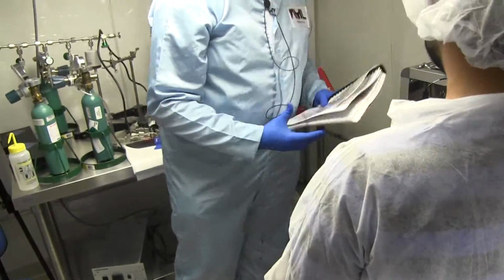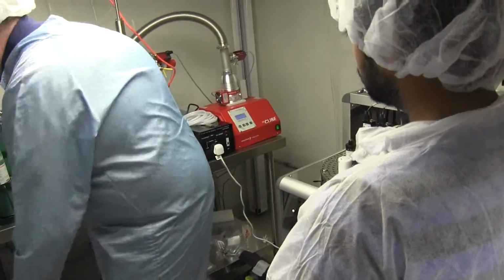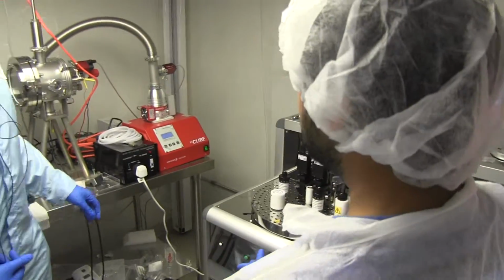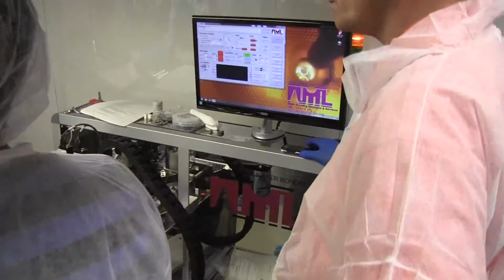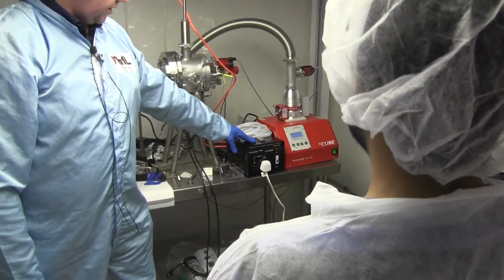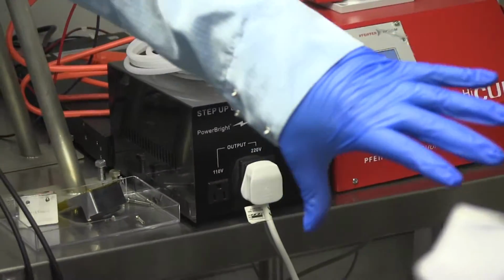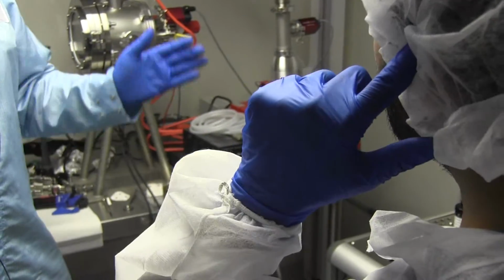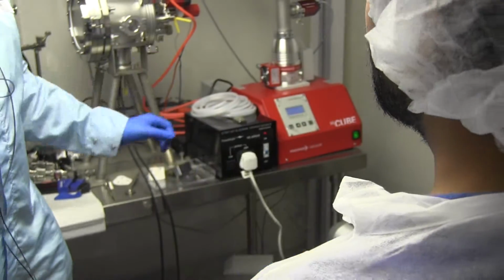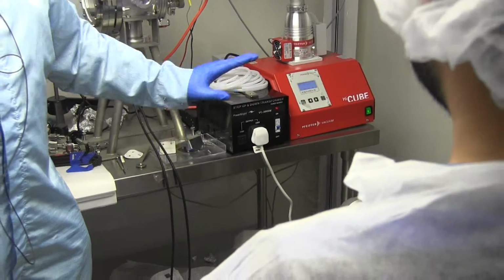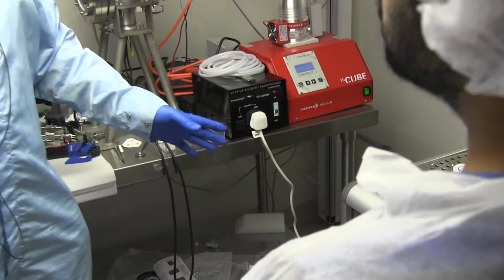In this case, mains voltage is approximately 246 volts, which is what's being output by this step-up transformer. Because the machine's built to European specs, UK specs, it requires between 200 and 250 volts, and your supply is 110 volts, so we're using this step-up transformer to power the machine without any modifications to anything else.